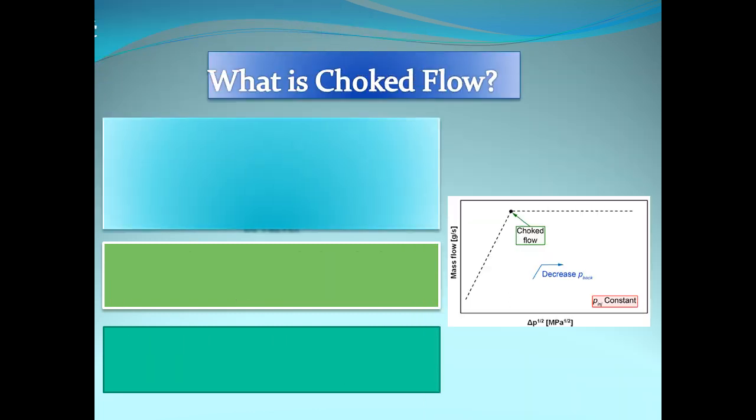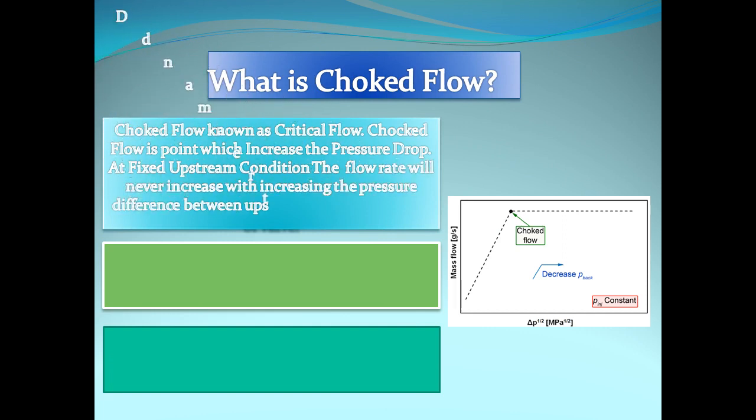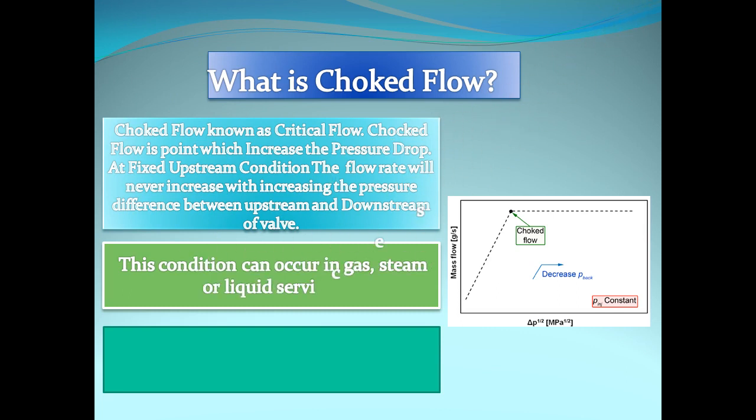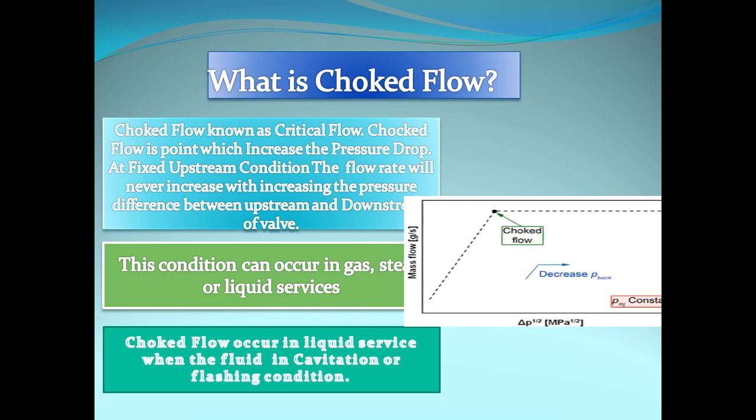What is Choked Flow? Choked flow is also known as critical flow. Choked flow is a point which increases the pressure drop. At fixed upstream conditions the flow rate will never increase with increasing the pressure difference between upstream and downstream of the valve. The conditions can occur in gas, steam or liquid service. Choked flow occurs in liquid service when the fluid is in cavitation or flashing conditions.